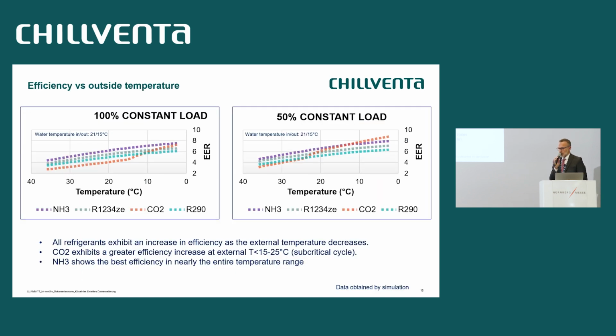So let's have a look at this chart. On the horizontal axis, you have the outdoor temperature. And be careful, the outdoor temperature is decreasing when you go towards the right. So you can clearly see that all the refrigerants exhibit an increase in efficiency as the external temperature decreases. And this is pretty obvious. In particular, we can see that CO2 has a jump, if you look at the orange line, towards 15 degrees, because CO2 is changing from transcritical to subcritical cycle. But basically, ammonia shows the best efficiency in nearly the entire temperature range.